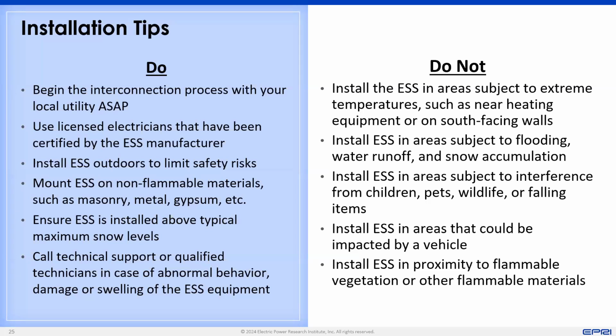Installing the energy storage system outdoors is a priority these days, not necessarily a requirement, but these systems can be dangerous. They can start fires, so they need to be installed behind firewalls. They can off-gas and release some nasty gases—there are dangers to lithium-ion technologies. Installing these systems outdoors alleviates a great deal of that risk.